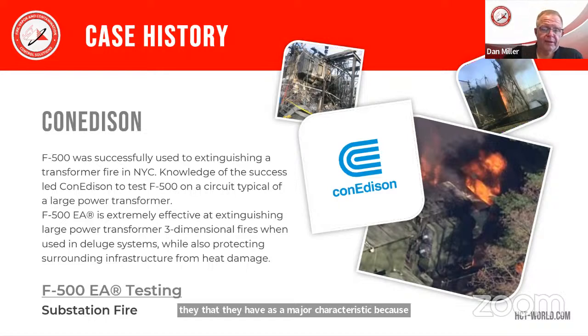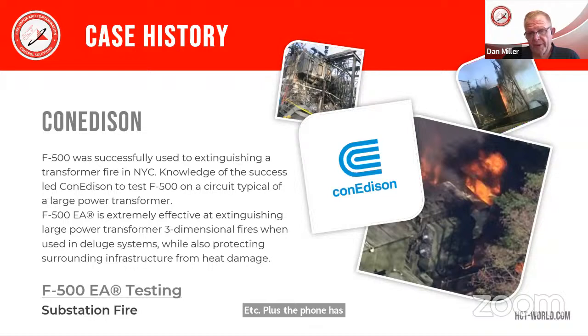It's a thing that foam is not very capable of, that three-dimensional fire, because it's hard to put a blanket on a moving object, a spraying object, etc. Plus, the foam has a tendency to hold the heat in. And when you're talking about a transformer fire, hot oil, hot steel, all of that in combination, you need an agent that cools really, really well, and F500 does that.